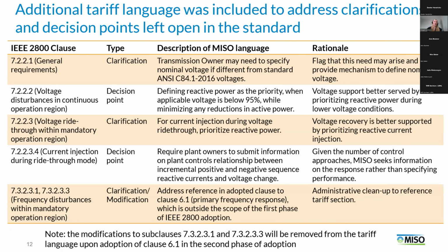So this is the summary of all the additional detail we added into the tariff language for adoption of clause 7 specifically. We made clarifications on 3 main items and then addressed 2 open decision points. So starting quickly just with the clarifications, for voltage ride-through, we clarified that the TO or transmission owner may need to specify what the nominal voltage is if it is not one of the standard voltages in the ANSI standard. Also for voltage ride-through, we made a clarification, basically just reiterating that we want all IBR plants to be in reactive power priority mode by default, as is already stated in the standard. And then the main clarification here is that we point to a place in MISO's GIA where it could be stated if the IBR plant is to instead operate in active power priority mode.